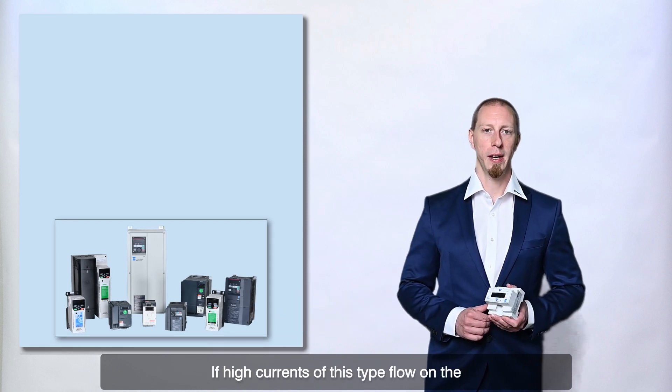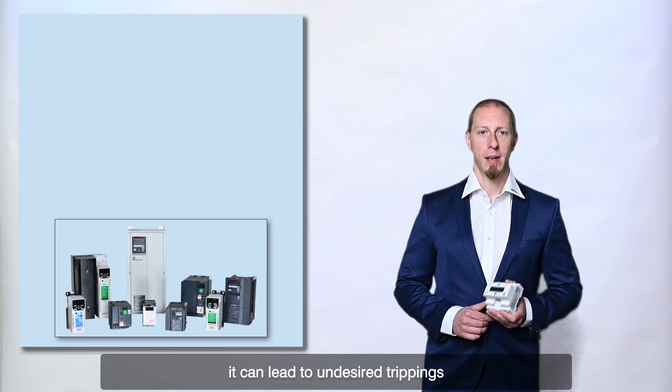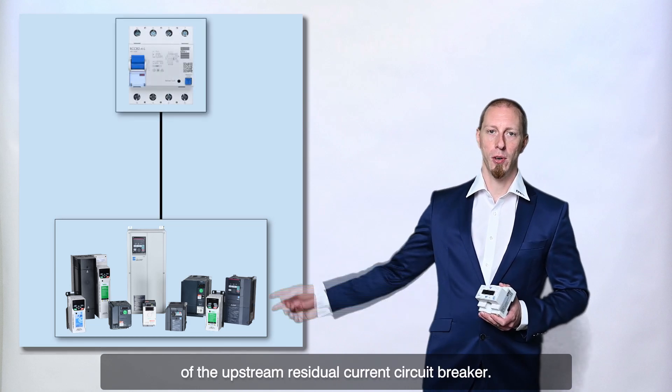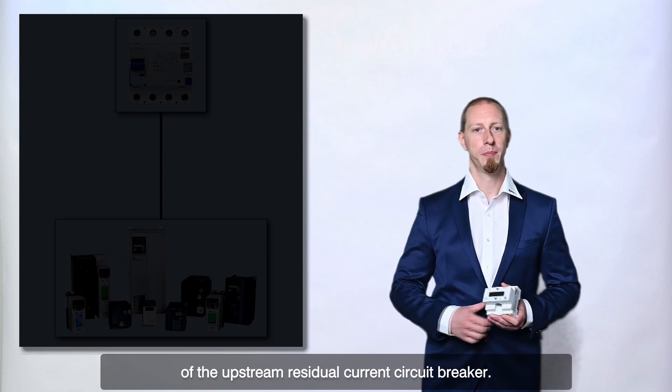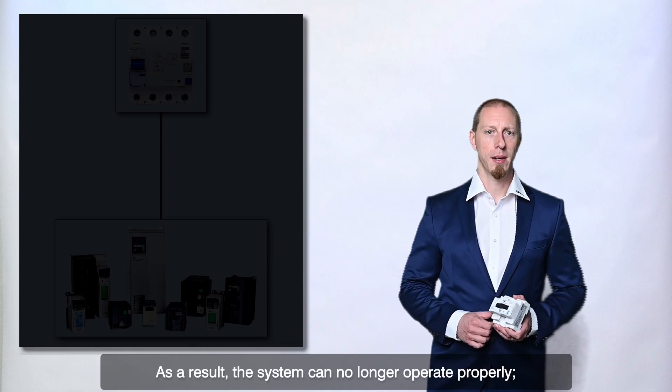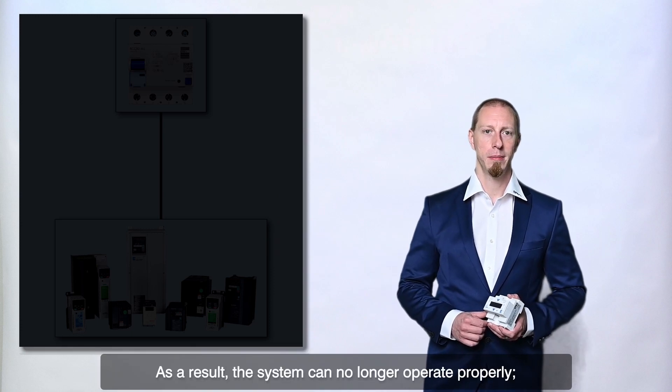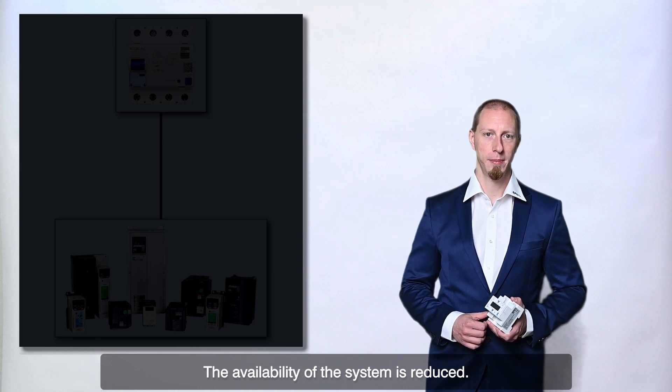If high currents of this type flow on the protective earth conductor of a plant, it can lead to undesired tripping of the upstream residual current circuit breaker. As a result, the system can no longer operate properly, the availability of the system is reduced.